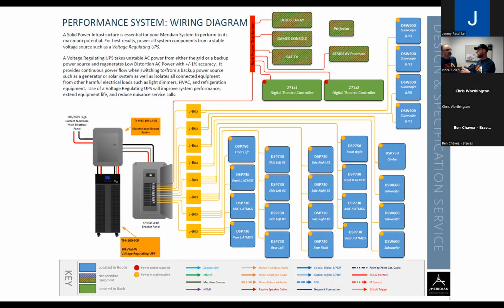From that moment on, Vince and I said, if you're buying a large format UPS, you probably want to do an external bypass. That allows that if anything were to ever happen in a bad way with that UPS, and you've got mains power, it just goes around the UPS and brings mains power to the connected load. It allows a technician to completely remove that UPS and maybe replace it with another one, depending on what the issue is and what they need to do.